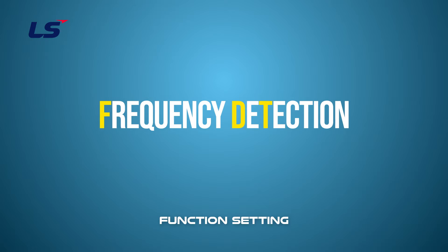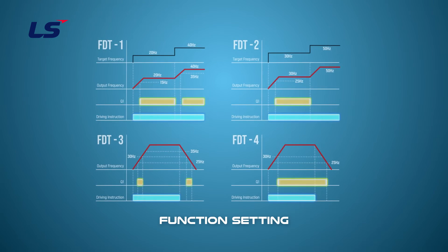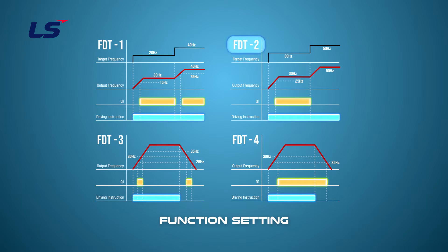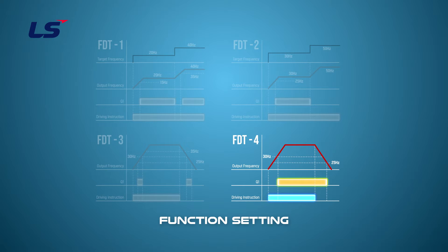Frequency detection is understood as the function to output a contact signal when a set frequency is reached. There is a total of four ways of exporting a contact output, and one function can be set between FDT1, FDT2, FDT3, and FDT4. The sequence used for dual brake control is FDT4.